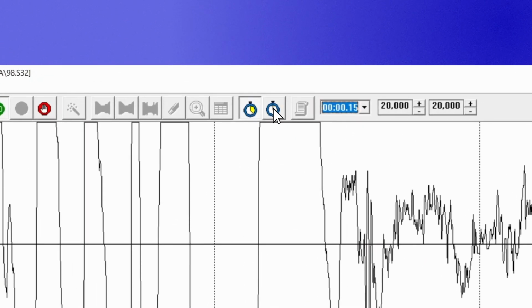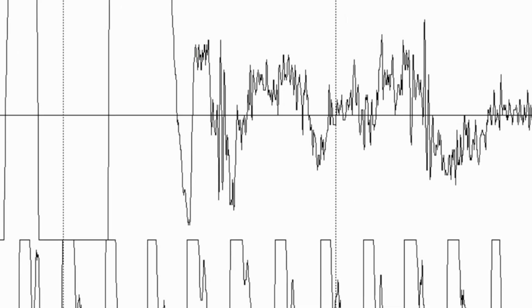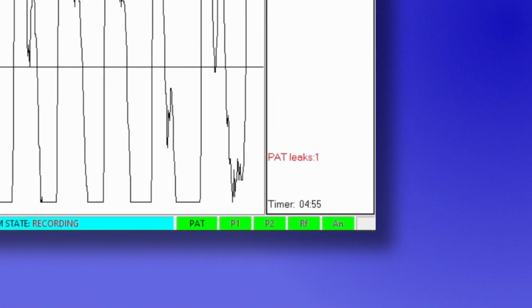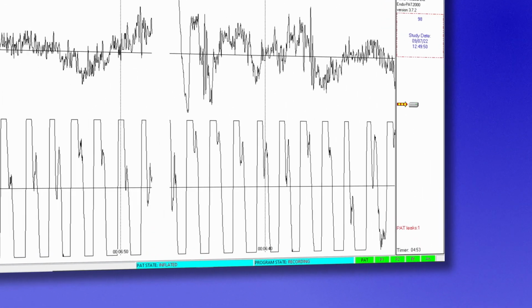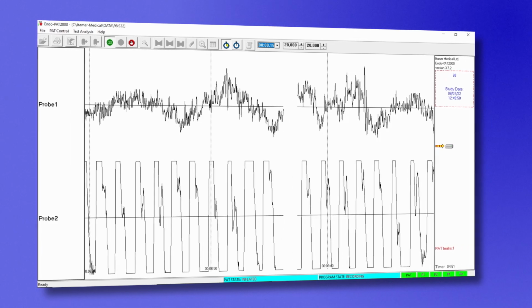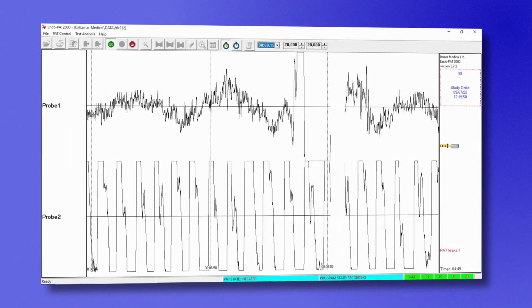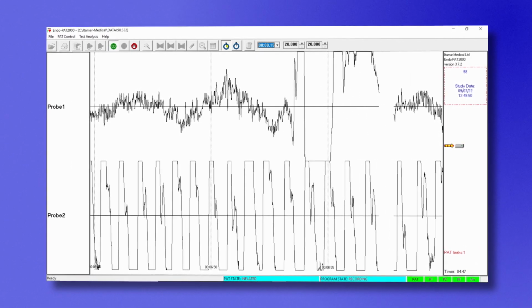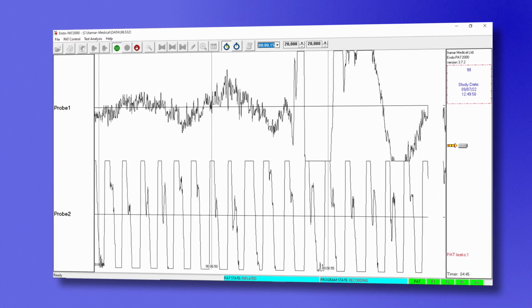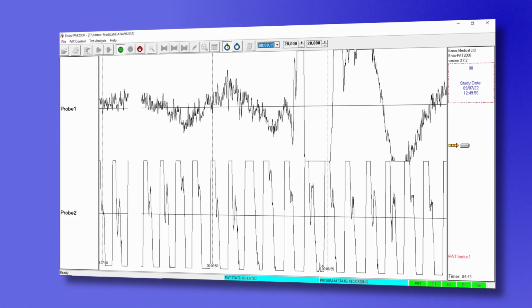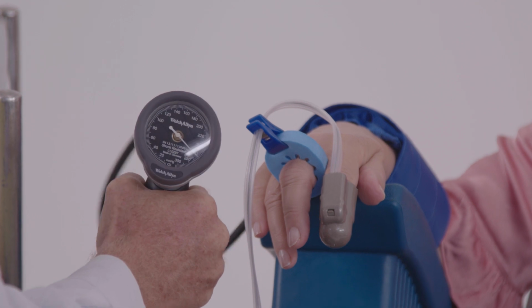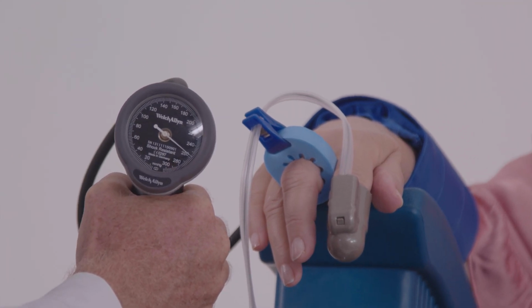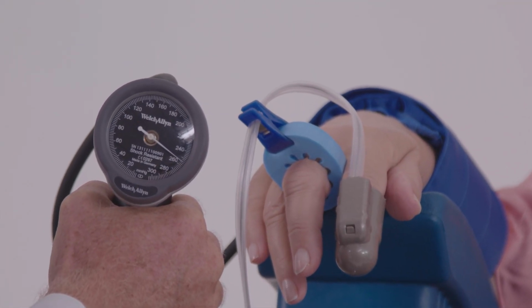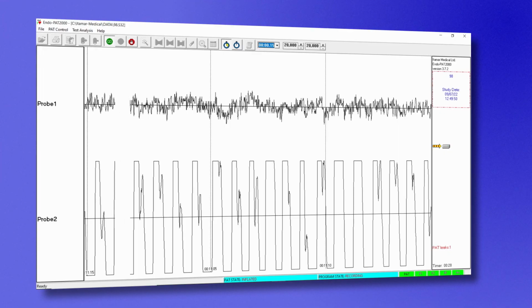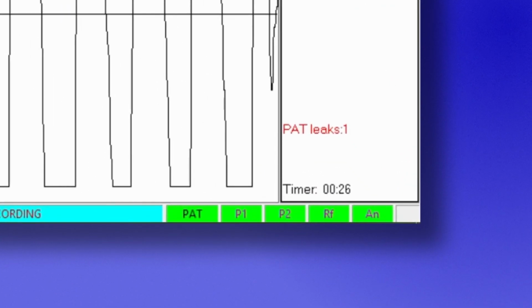Press the stopwatch button. This will set a timer for the 5 minutes of the occlusion phase. Compare the signal between both probes. Notice the occlusion is complete when there is no correlation of peaks between the occluded and non-occluded hand. If the occlusion is not complete, increase occlusion by 50 mm of mercury up to 300 mm of mercury. Occlusion duration will remain 5 minutes, even if adjusting was needed just before the end of occlusion time.